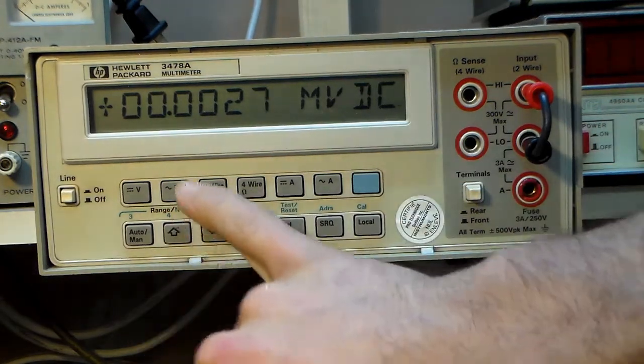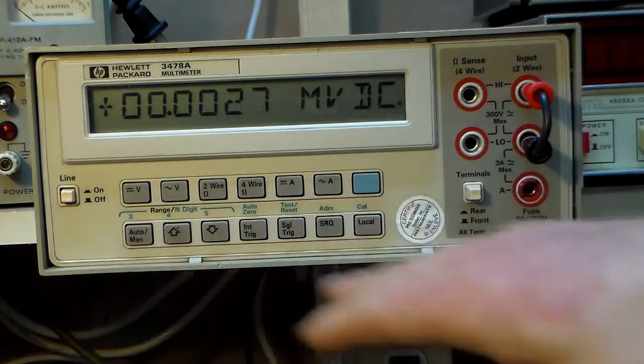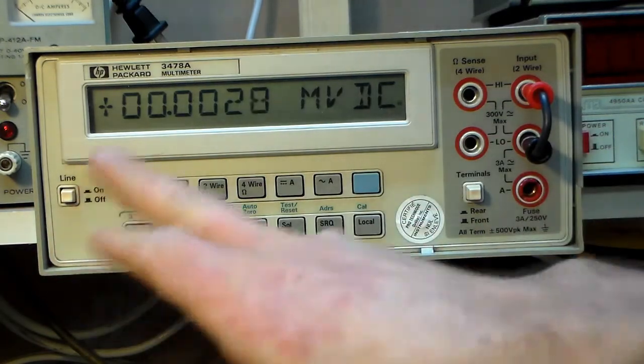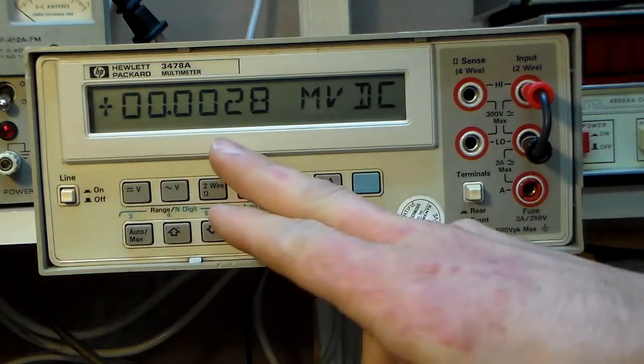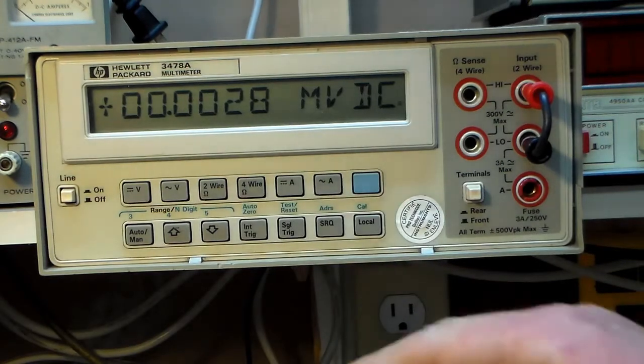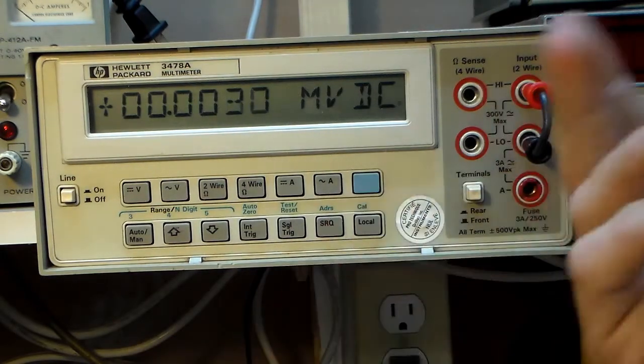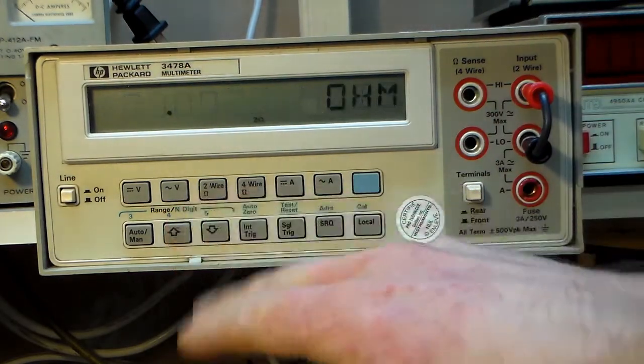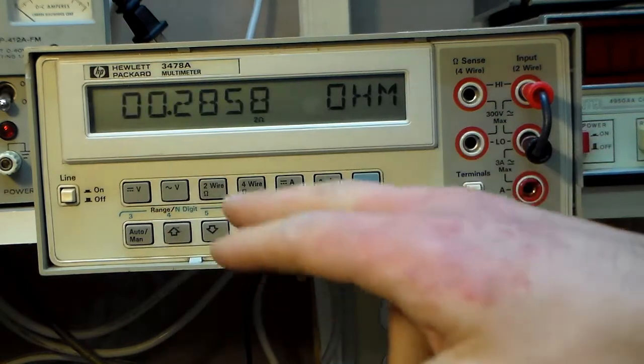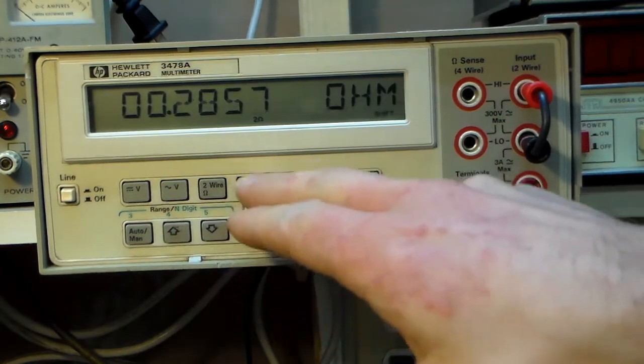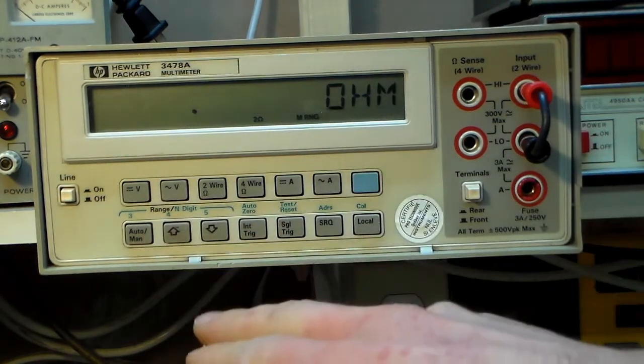And it works not only in two-wire mode, it works in any mode. It just uses whatever is displayed as an offset. So that also means if you're changing ranges, it won't work. So if I go back to resistance, save the offset if I range up.